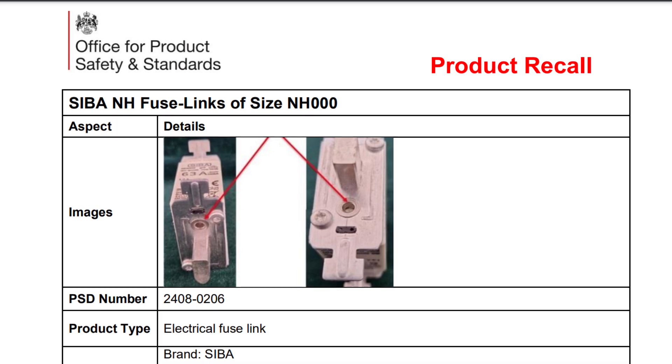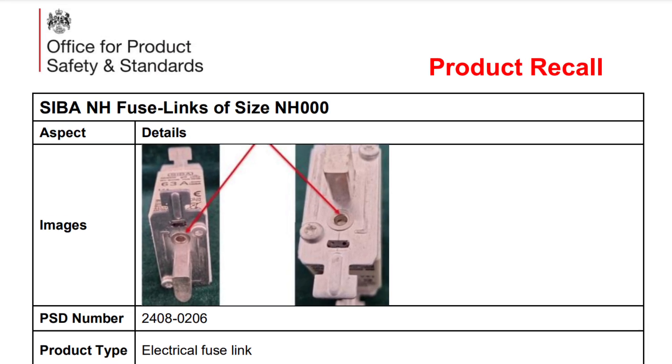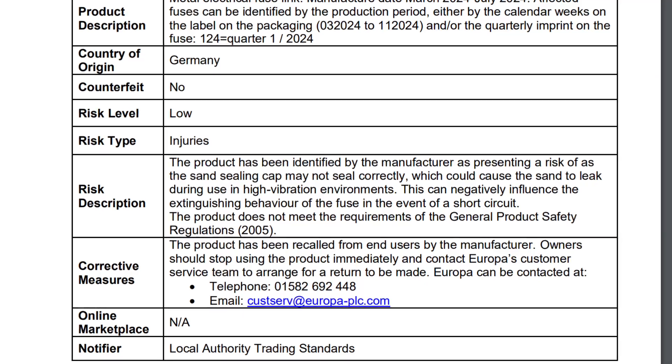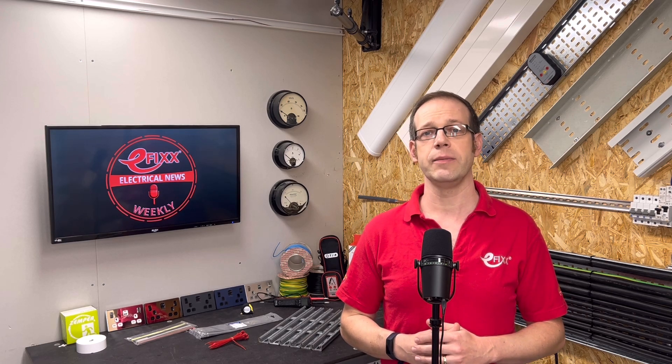In product news this week, German manufacturer SIBA is recalling a batch of its fuse links over safety fears. The issue was flagged up by UK trading standards. The metal links, size NH000, were available to purchase from April to July this year. The product has been identified as presenting a risk because the sand sealing cap may not seal correctly, which could cause the sand to leak during use in high-vibration environments. This can in turn negatively influence the extinguishing behaviour of the fuse in the event of a short circuit. Electricians should tell their customers to stop using the product and contact the customer service team to arrange for it to be returned.